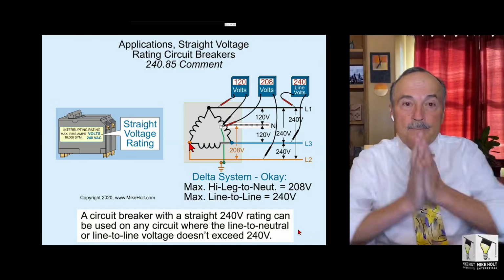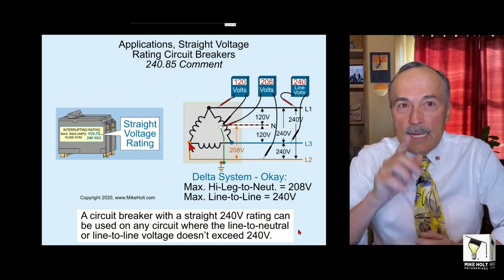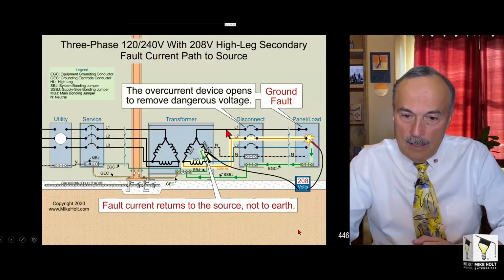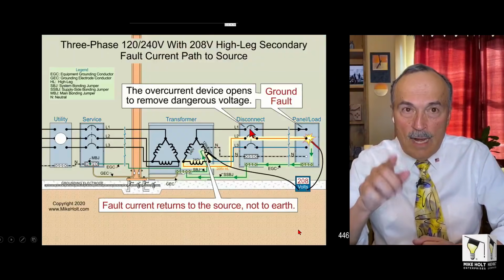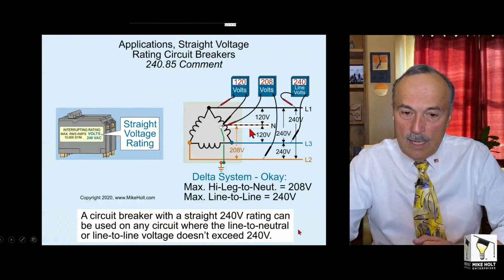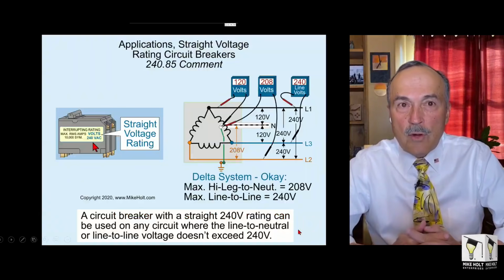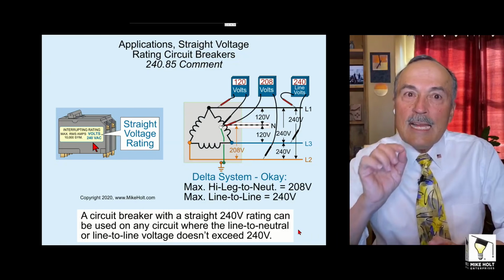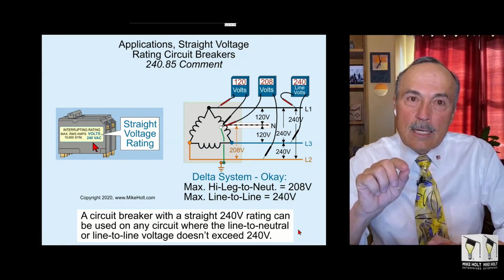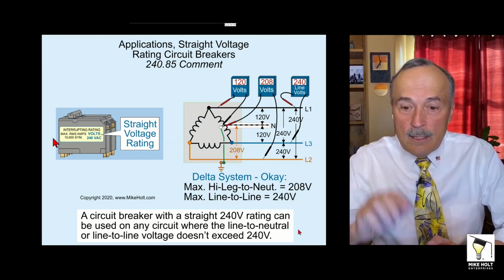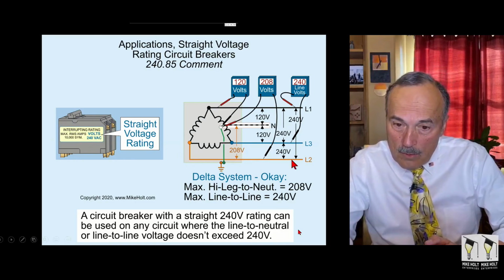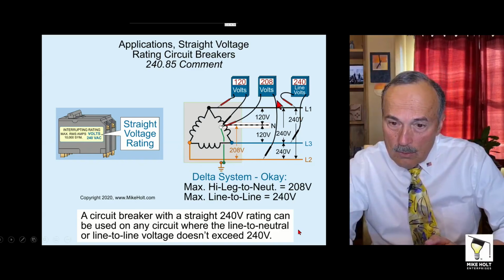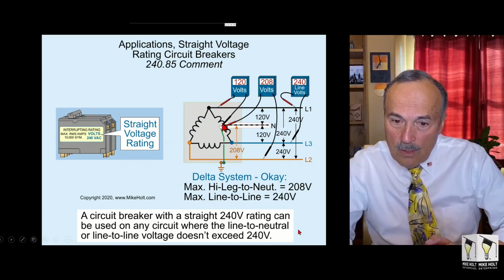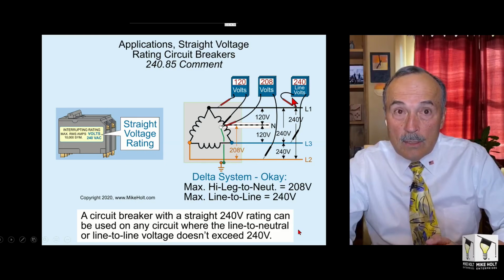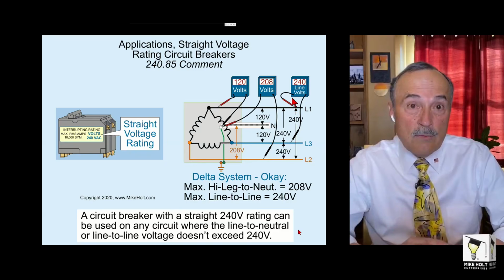Okay, sorry about that. Delta high leg. If there's a fault from the delta high leg back over here, that means the ground fault voltage is going to be 208. Voltage to ground is 208, and the phase-to-phase voltage is 240. So straight rated breakers are fine for the high leg.